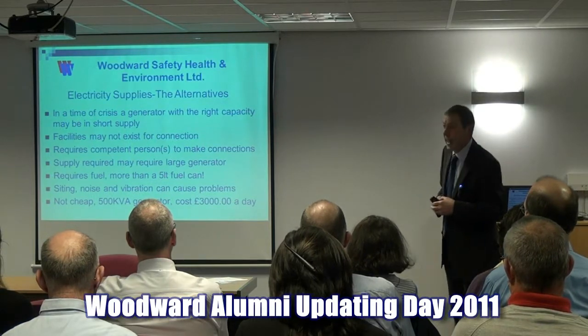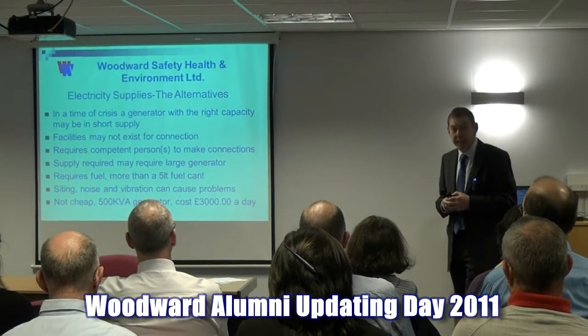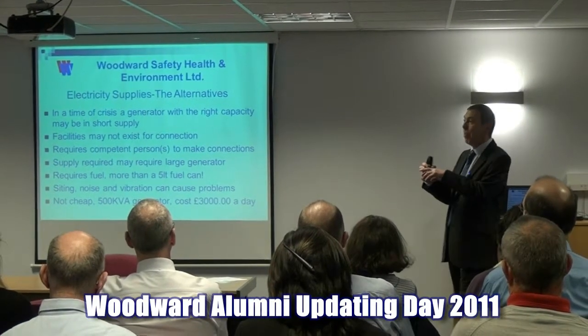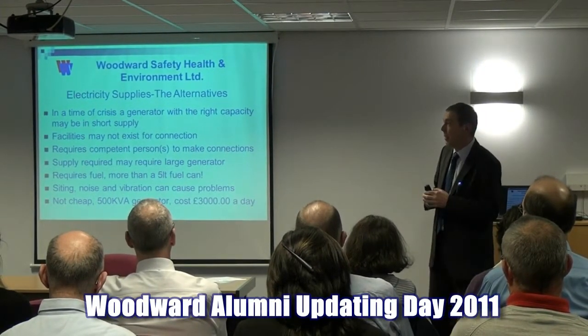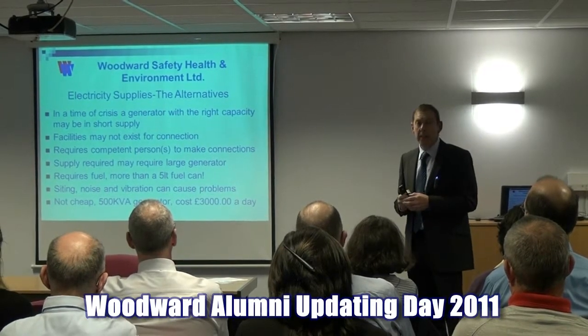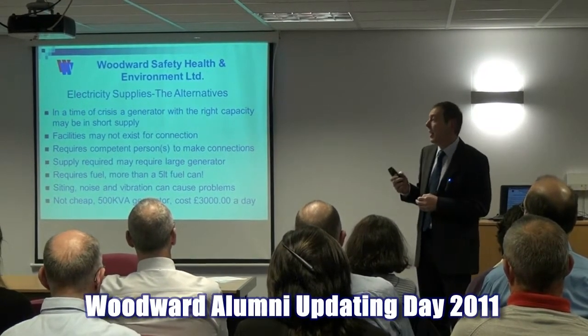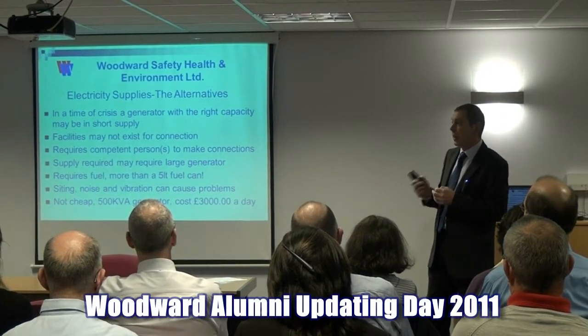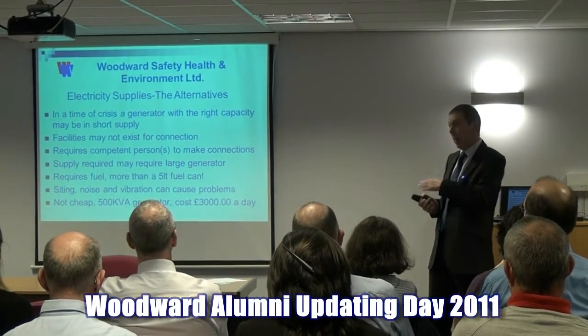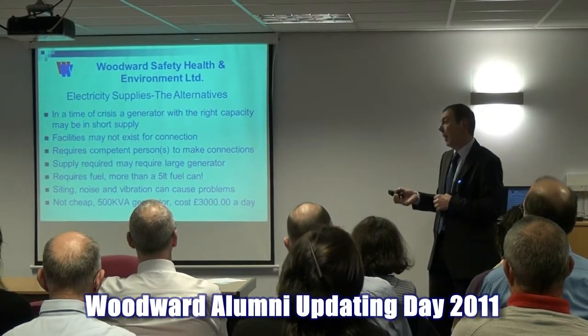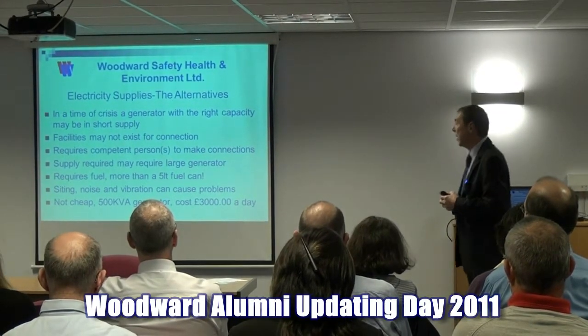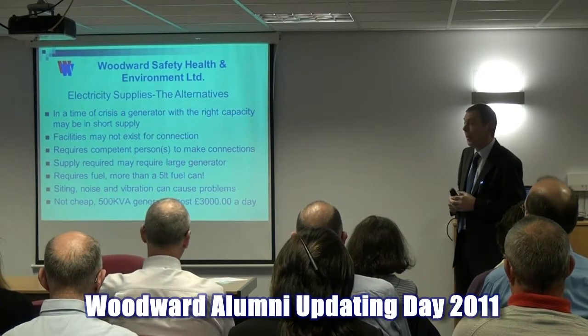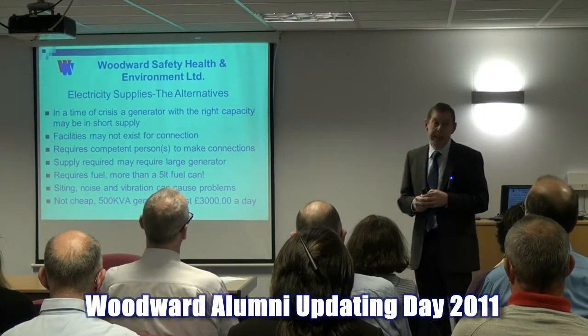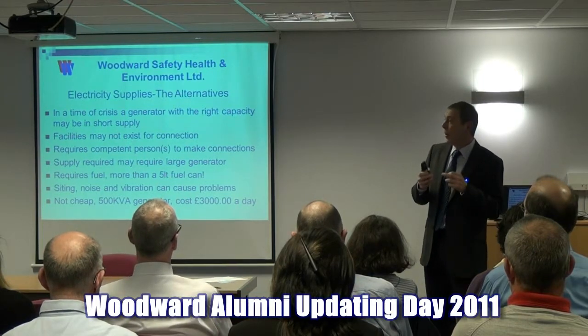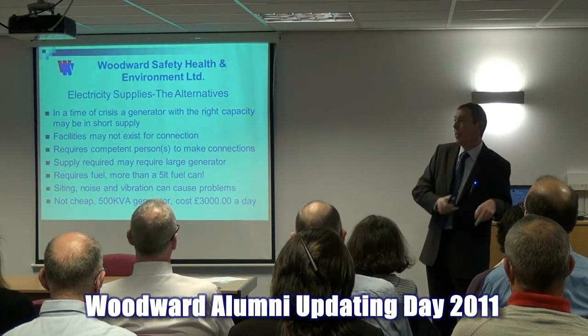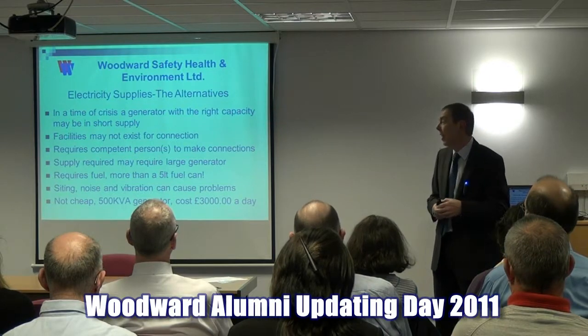Facilities may not exist for connection. We did have them. We had existing connection facilities within our plant room where the electricity supply came into the building. We'd already catered for an instance like this, maybe not of this size, but we'd already thought about whether we could substitute and change over from mains electricity to an emergency standby supply, and do it in a safe manner. Did we have competent persons? Yes, we ticked all the boxes on that. I had a charge hand electrician and an electrician with me who had actually already installed and modernised the very plant room we wanted to connect the generator up to.